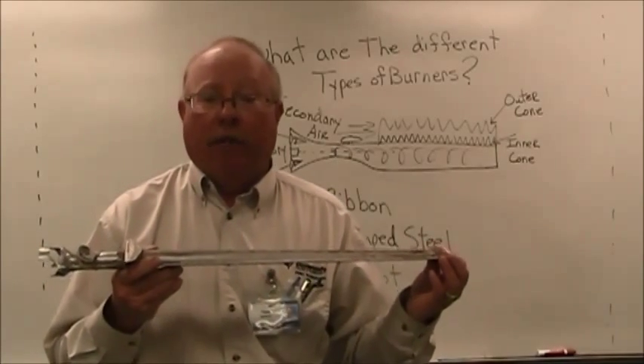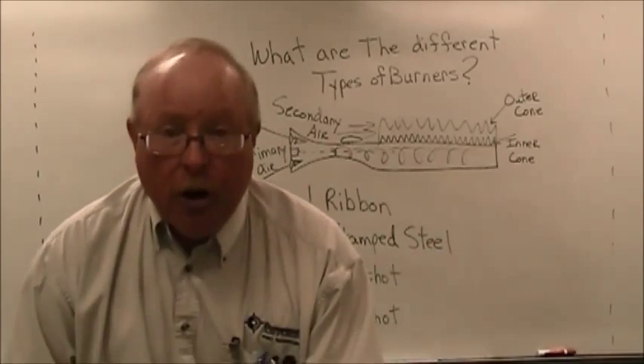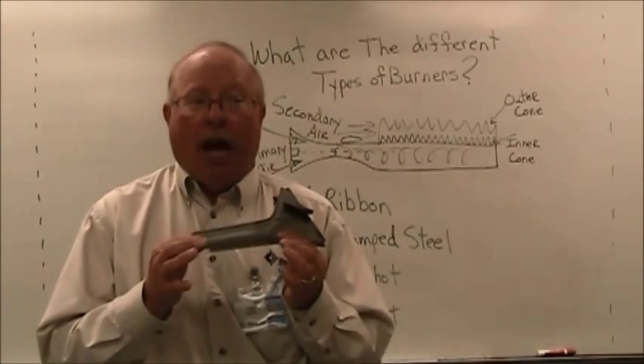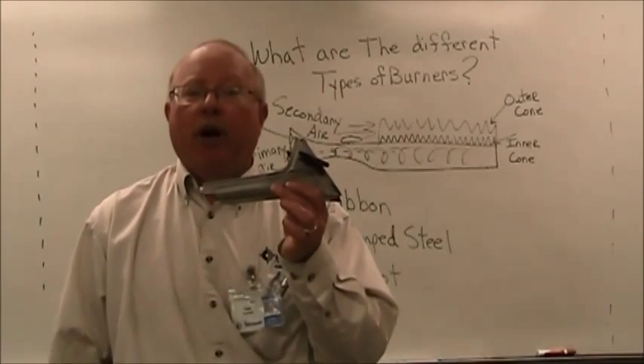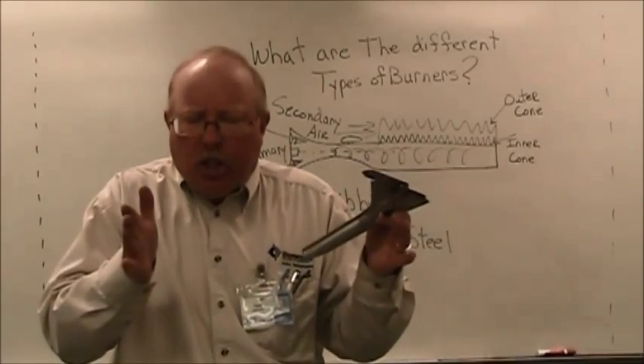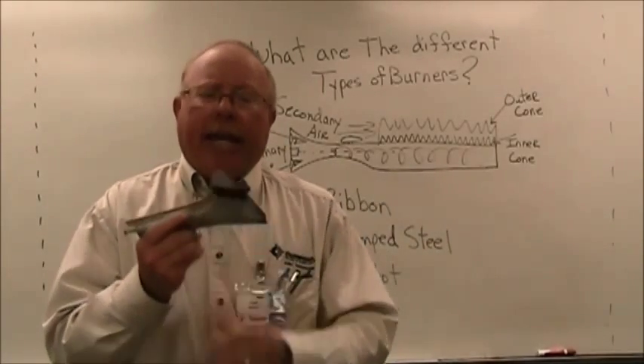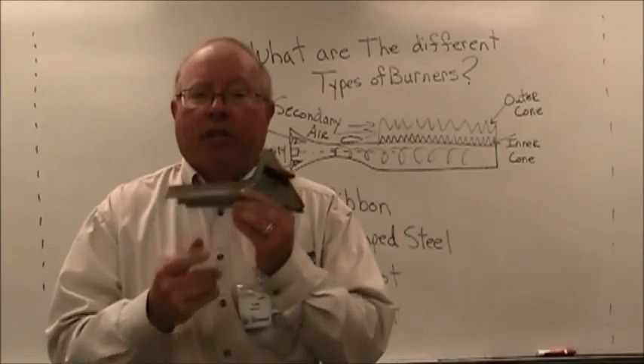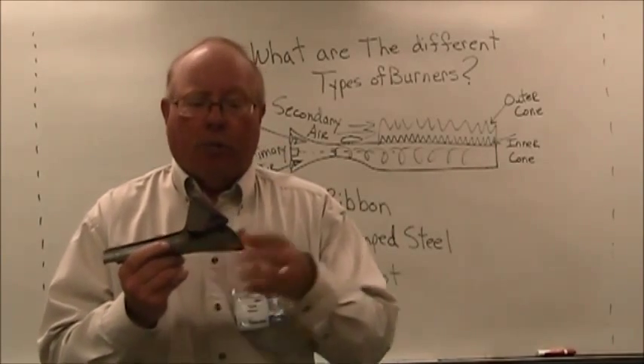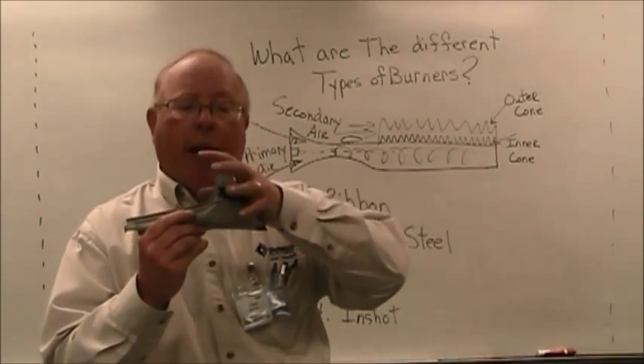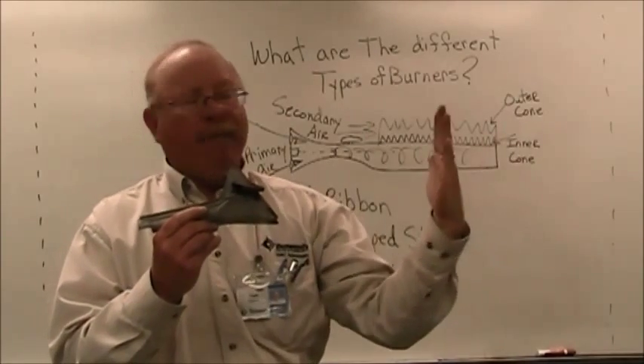Third, we have the upshot burner. This particular burner is going to be used in fairly short heat exchangers. It gets its name upshot because of the single ported burner with no spreader on it allows for the flame to come out and then move up immediately.